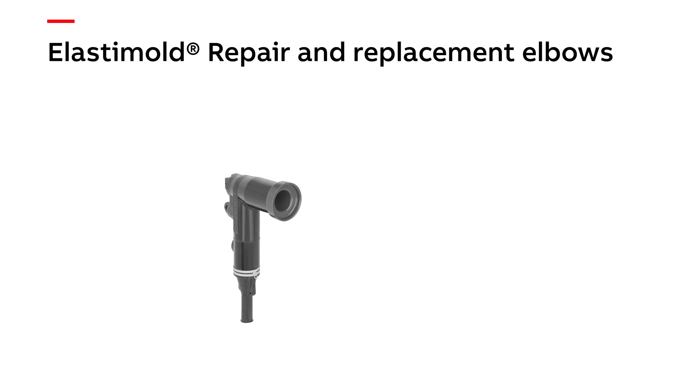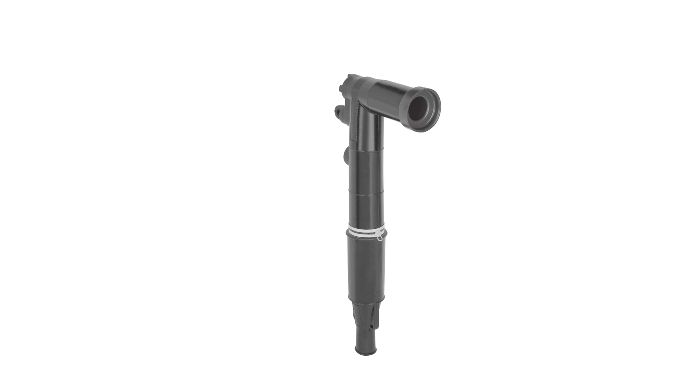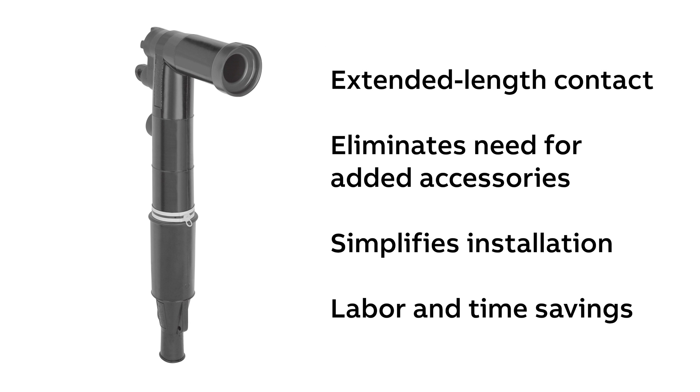I mentioned elbows, but let's talk about repair and replacement elbows, which are a bit different. Let's say you're replacing switchgear and the new switchgear connection points aren't in the same place as the old switchgear, and now you find yourself in a situation where your cables don't quite reach. Elastimold replacement elbows are made for this — they give you that extra length you need so you don't have to splice or pull the cable.